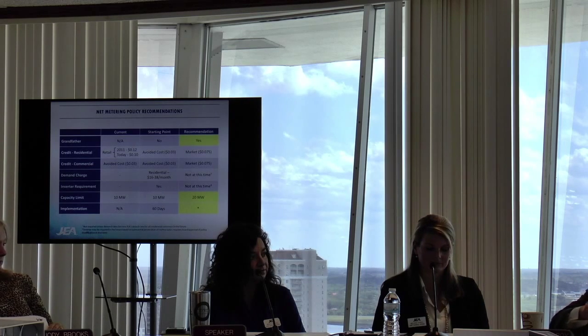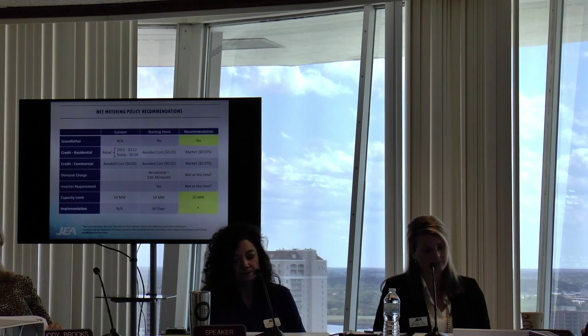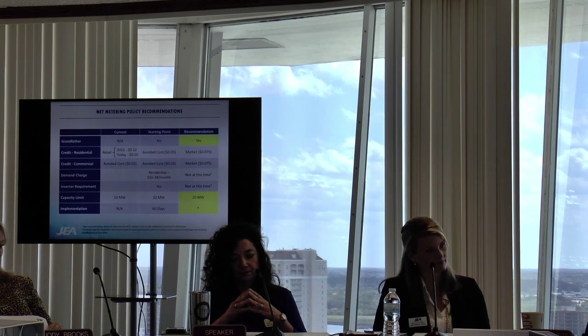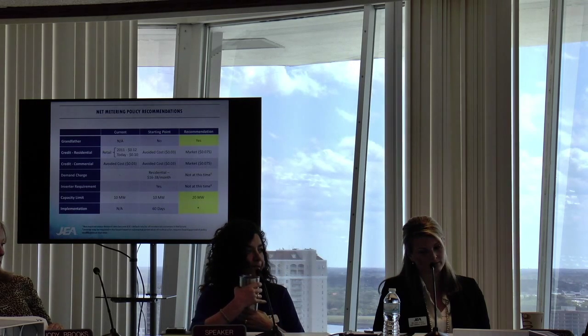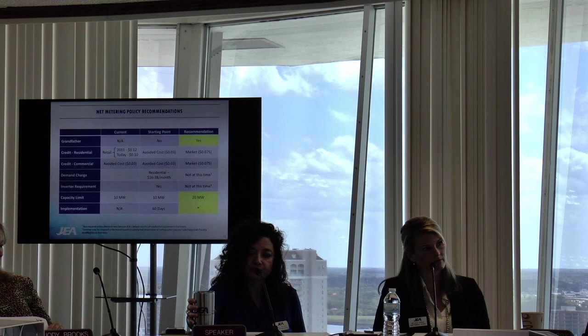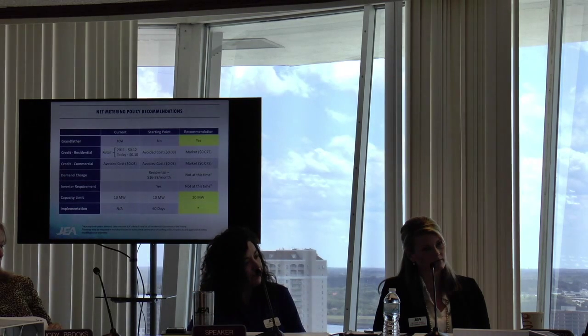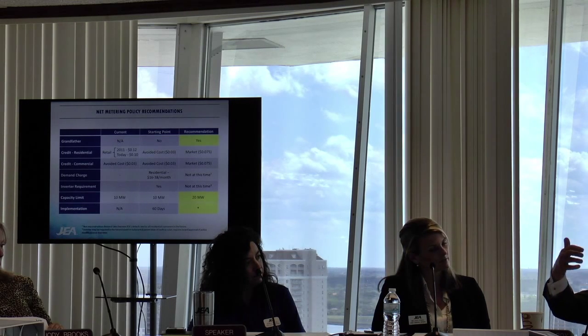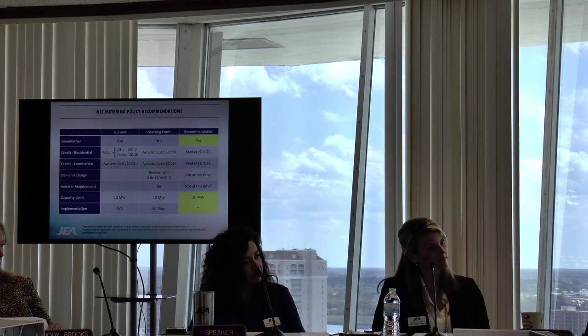If I can give a little clarity on the 10 megawatts. The pause button now would be for system reliability, and it's the time to assess the system reliability depending upon where the installations occur. We get a very different impact on the system if we have a circuit with 20 individuals on it and 15 of those have solar, versus 20 circuits with one on each circuit. It has an impact on power quality and reliability.